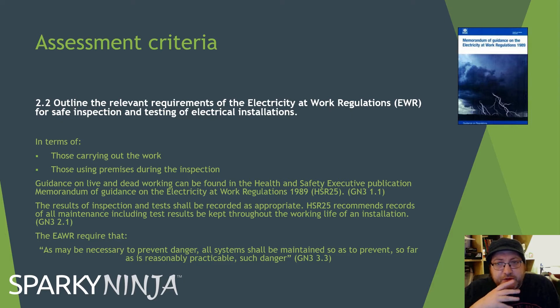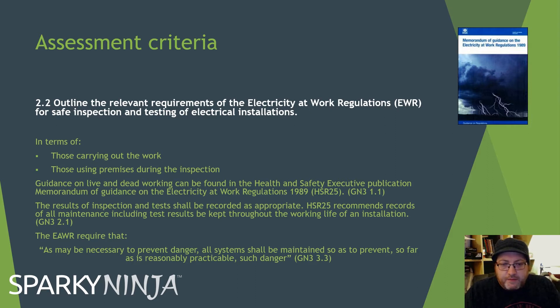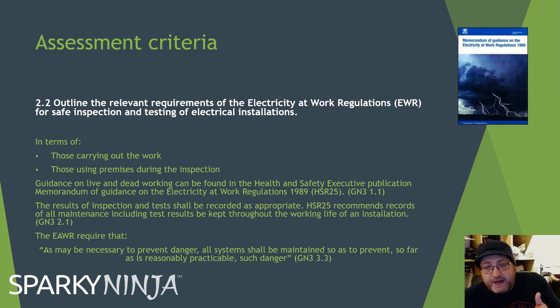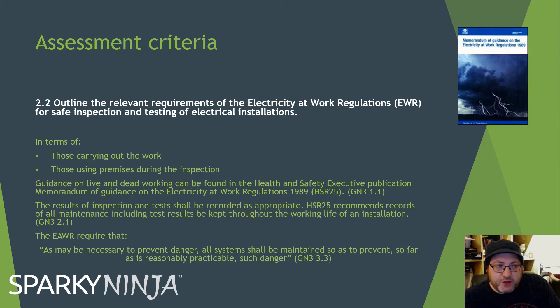Those using the premises during the inspection must also be considered. If you're working on a site and going to open panels or do insulation resistance testing — creating potential differences within the system — you've got to identify risks to persons at work. You must either remove them from the area or inform the site's responsible persons of these risks so they can put in safety protocols.